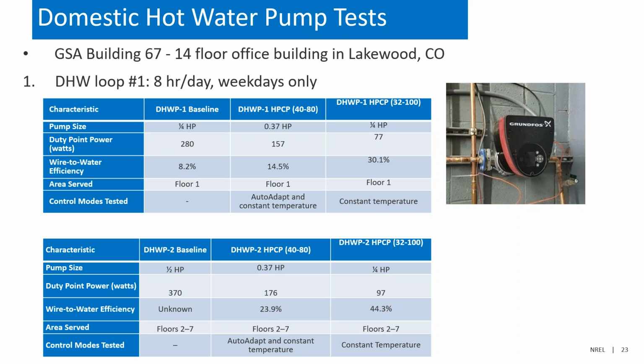You do see that with the wire to water efficiency numbers. Wire to water efficiency is essentially the pump efficiency multiplied by the motor efficiency. And when you're operating in scenarios with high differential pressure and low flow rates, you're running on a very challenging point of the pump curve. And so normally you do have lower wire to water efficiencies than on larger central plant pumps, for example. But you'll see on the first one, we did improve from 8.2% all the way up to 30%. The domestic hot water pump number 2 had about double the flow rate of the smaller domestic hot water pump number 1. And so you'll see it was able to operate at an even higher wire-to-water efficiency there. But I think the main takeaway on this is we saw very significant reductions in pump power at the peak load for those pumps.